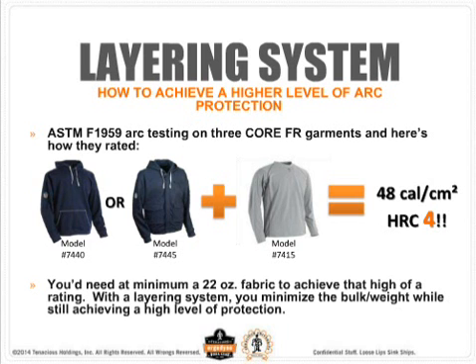To equal this high of an ARC rating with one garment, most likely you would need to bulk up and get a garment with a minimum of 22-ounce fabric, so it's extremely heavy and kind of uncomfortable. That's the advantage of wearing a layered system: you help to minimize that bulk and weight, yet you're still able to achieve a higher level of ARC protection.